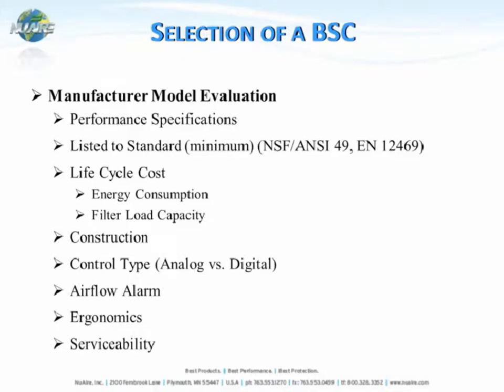In the United States and Canada, the relevant standard is NSF/ANSI 49; in Europe it is the EN standard. When looking at lifecycle cost — a biological safety cabinet has an average lifecycle of about 15 years — consider the energy consumption of the cabinet and the filter load capacity. The biggest expense after the initial purchase is changing HEPA filters after they load. Will filters load in 3 to 5 years, or will they last up to 8 to 10-plus years?